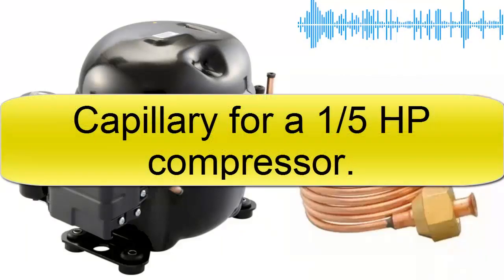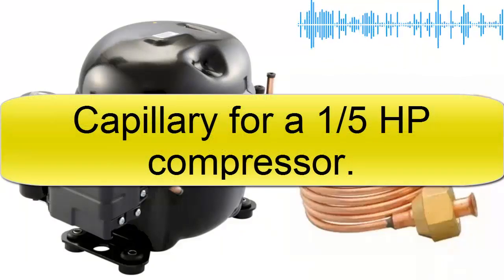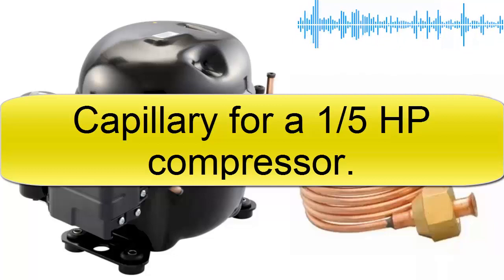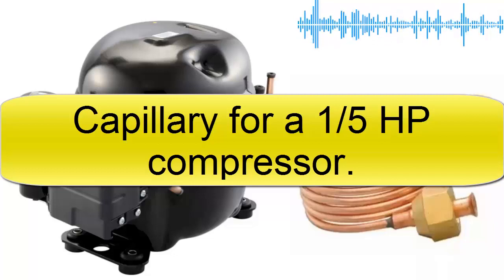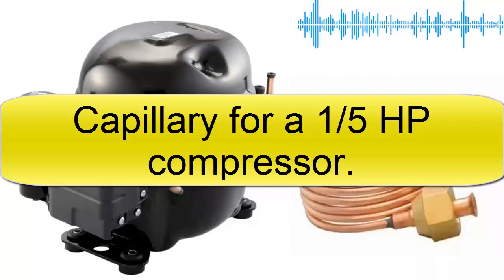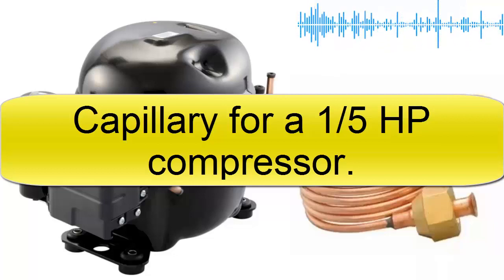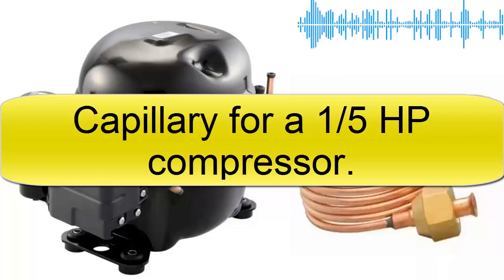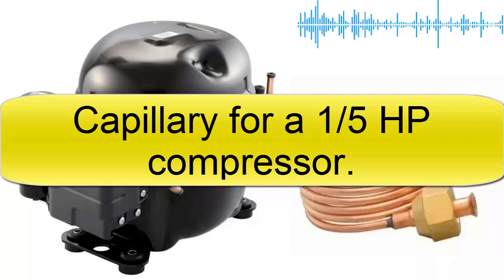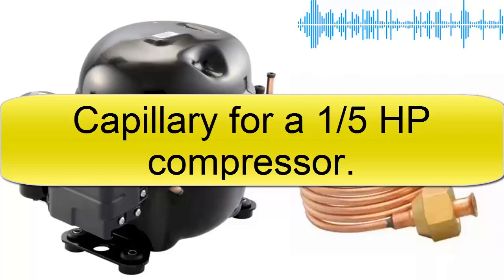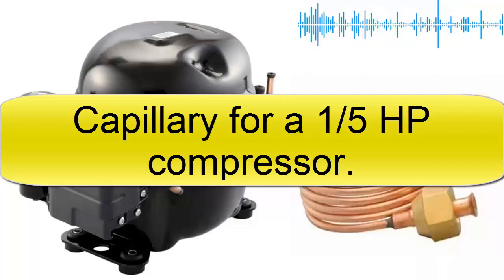Today we present capillary measurements for a one-fifth of a horsepower compressor. The measurements depend primarily on the type of refrigerant gas, the evaporation temperature, the condensation temperature, and the cooling capacity of the compressor. Taking these conditions into account, we will present the following measurement tables.